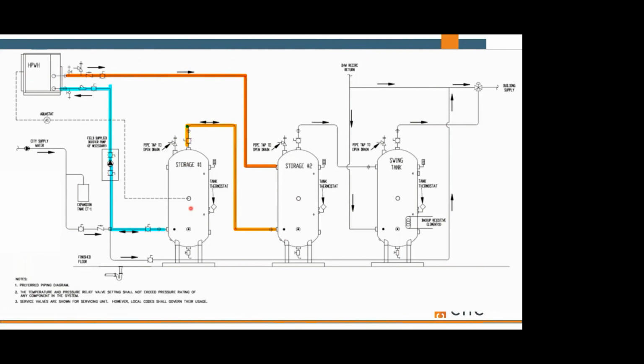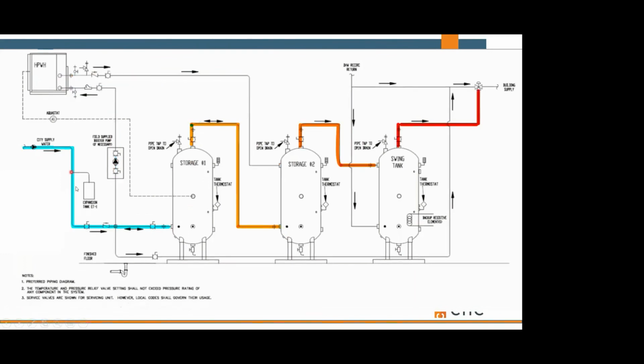Now, when there's a load in the morning, people are jumping into the shower and they're looking for hot water. You've got city water that comes in and starts pulling hot water out of storage tank number 1, sending it over to storage tank number 2, and possibly into what we might call a swing tank. And all a swing tank is, it's kind of a final tank to make sure we've got some hot water available for our system in case things go wrong in the middle of the night, or there's a really big load that exceeds our design. So a swing tank typically has some type of backup heat, whether that's a dedicated gas water heater or electric coils in there, something to make sure we're maintaining 140 in our swing tank. Okay.